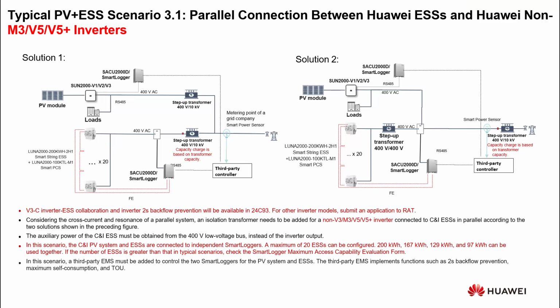It's because our inverters, if you analyze the circuit diagram, have only three-phase wires and the PE wire—there is no neutral wire into this inverter because it's not needed. Our inverters are a symmetrical source of power, so the neutral wire is useless in such a case. And if we use our battery in a scenario with only balanced charging or discharging, of course, it depends on the business model we use.